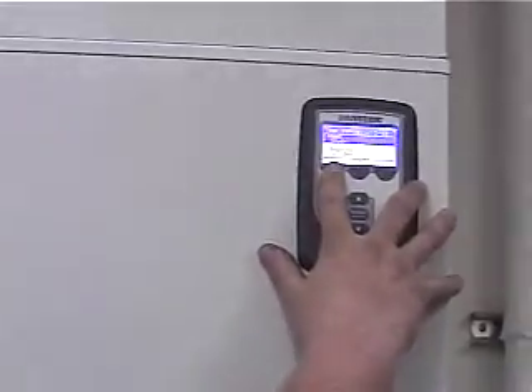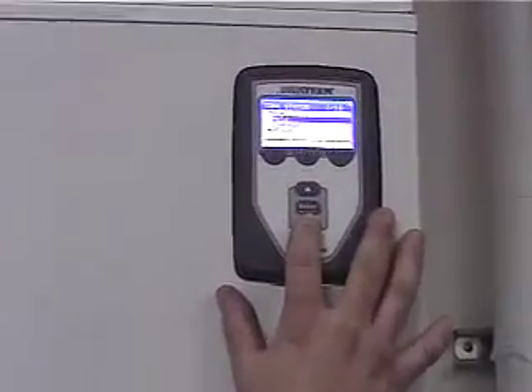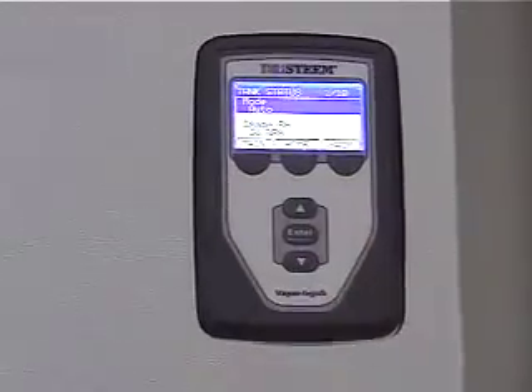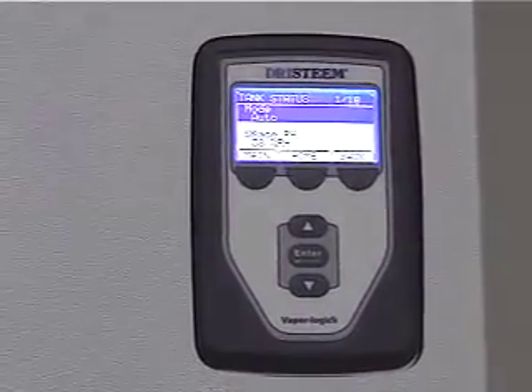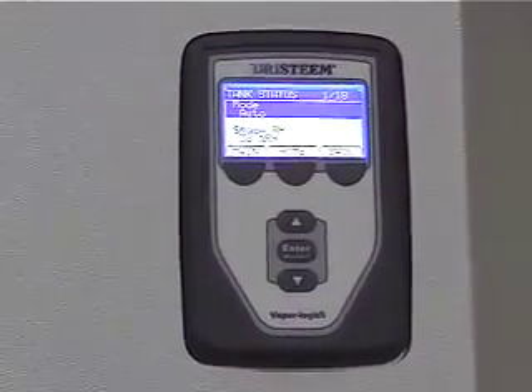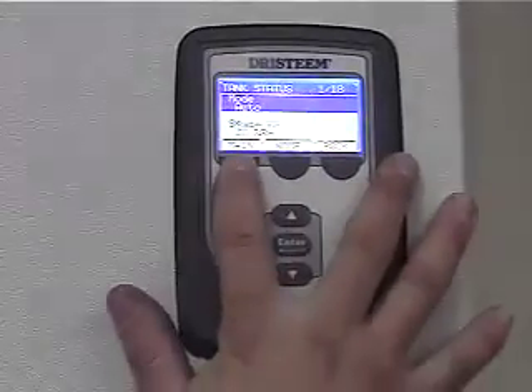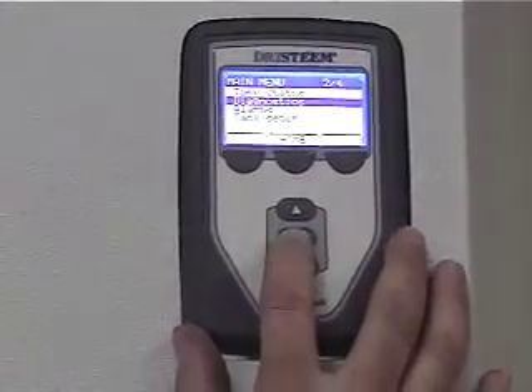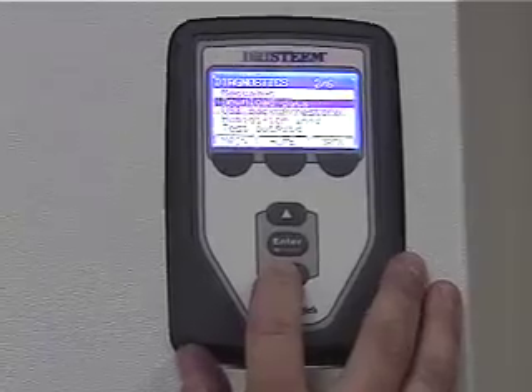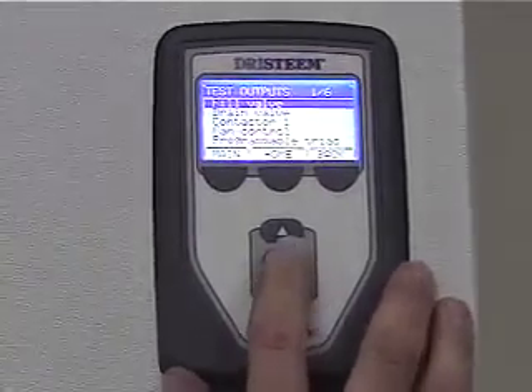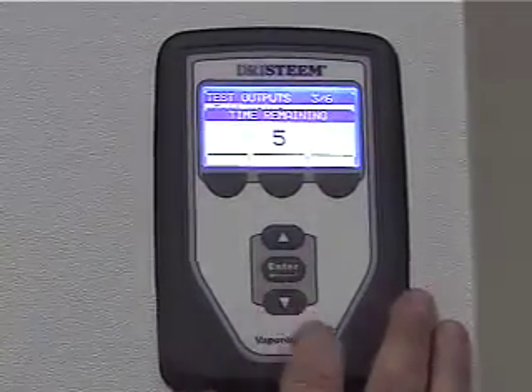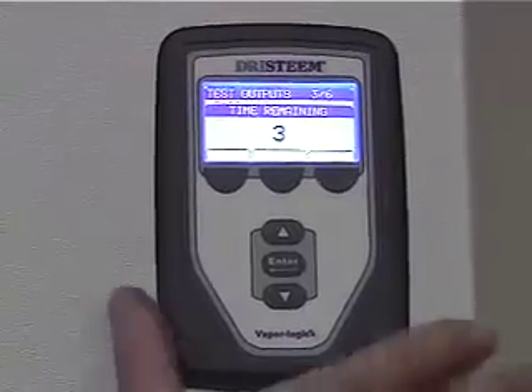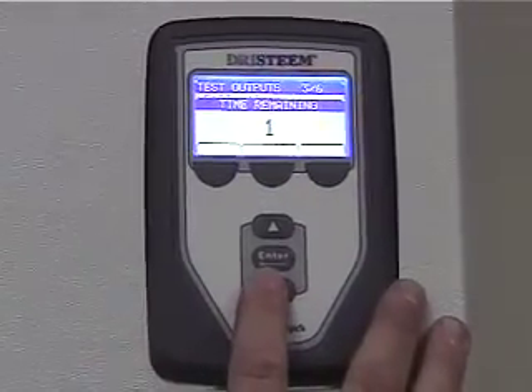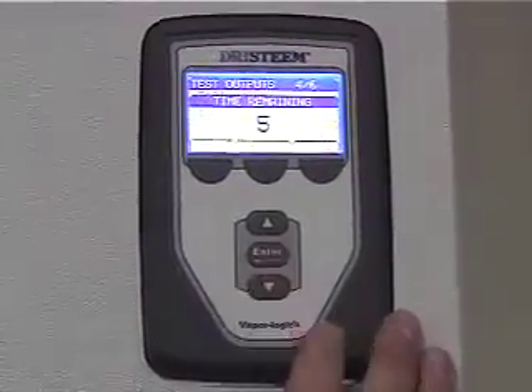Let's get back out of here and go back into auto, and hear the fill valve kick on. Now it's filling back up because we're a little bit low. I can come in here and go into diagnostics, and then go down to test outputs. So I can test my fill valve, I can test my contactor. Anything you want to know about whether this thing's working, we can test it, including fan control.